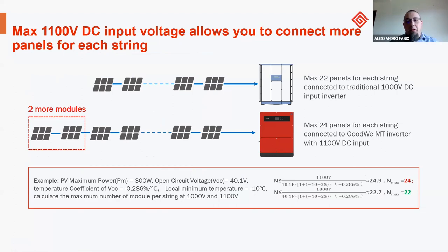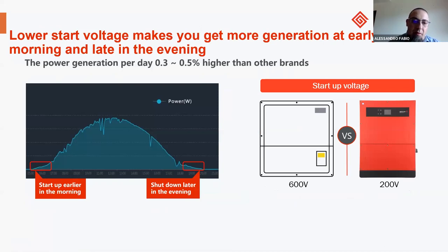Another point, for large scale but not only, is the starting voltage. With our inverter, we start with 200 volts. So we can produce more at the beginning of the morning and then in the evening, because we have a really low starting voltage to feed energy into the grid. This is also really important, because you start to produce early in the morning and later in the evening.